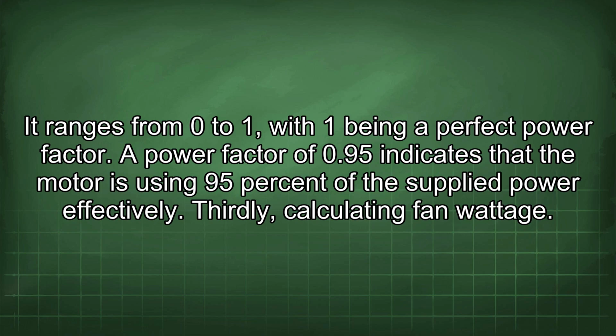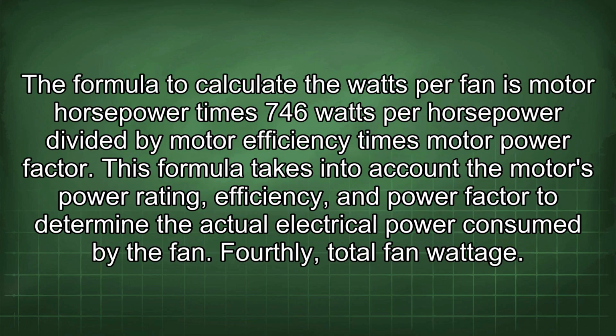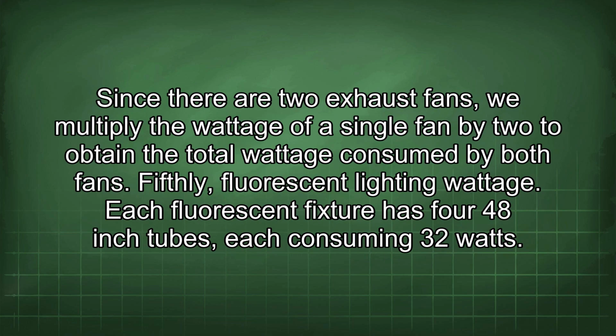Thirdly, calculating fan wattage. The formula to calculate the watts per fan is motor horsepower times 746 watts per horsepower divided by motor efficiency times motor power factor. This formula takes into account the motor's power rating, efficiency, and power factor to determine the actual electrical power consumed by the fan. Fourthly, total fan wattage. Since there are 2 exhaust fans, we multiply the wattage of a single fan by 2 to obtain the total wattage consumed by both fans.